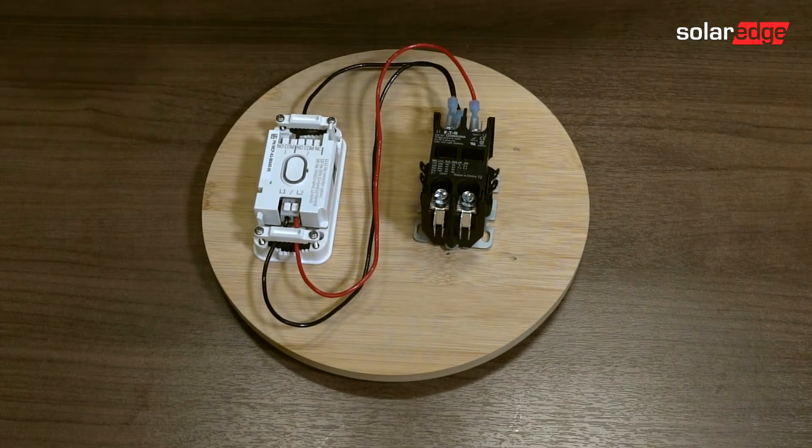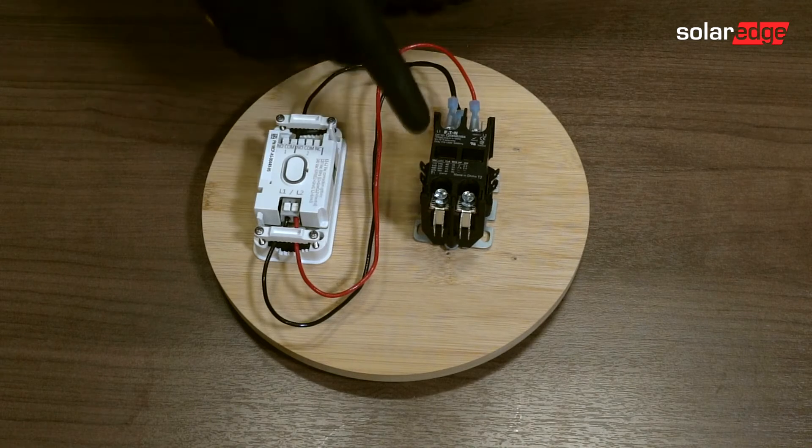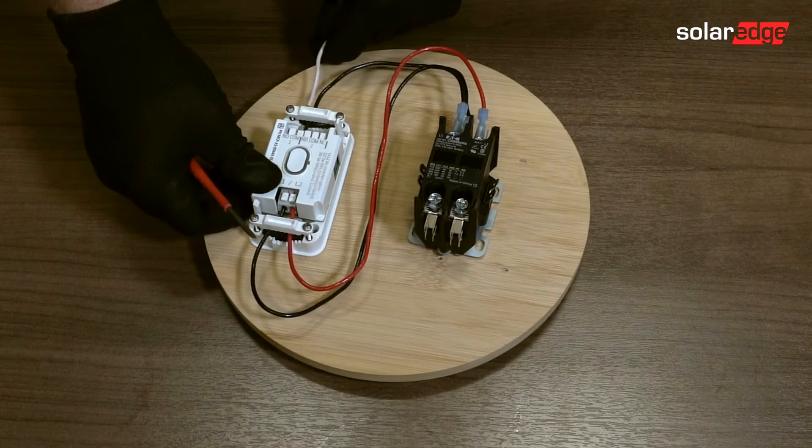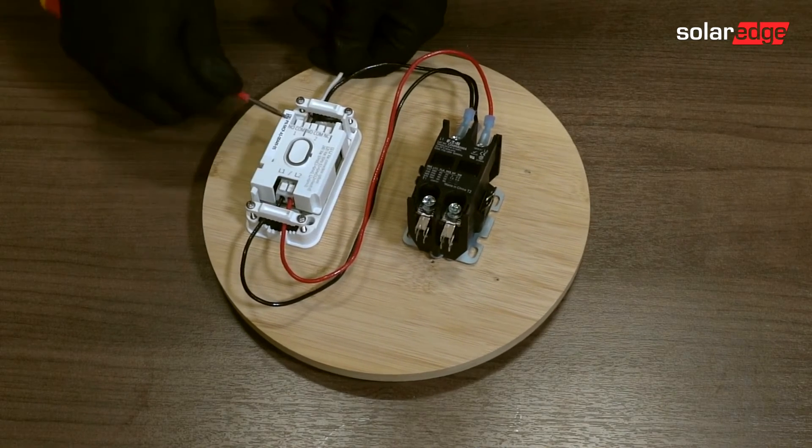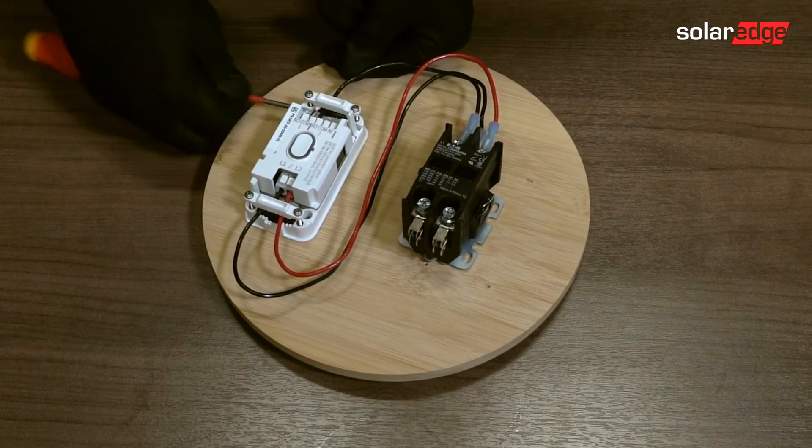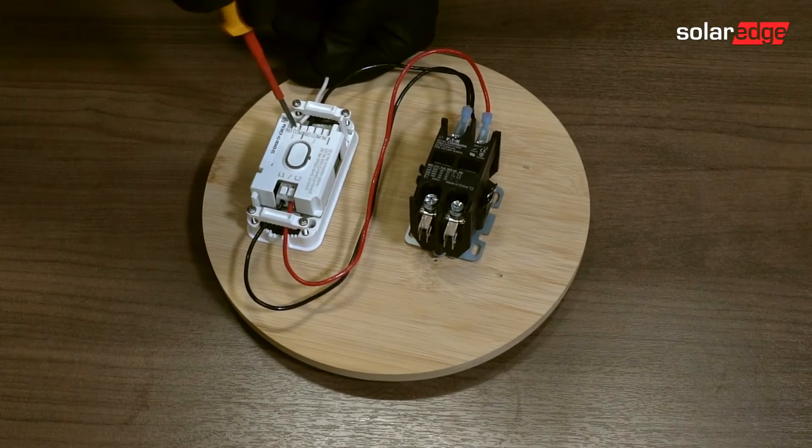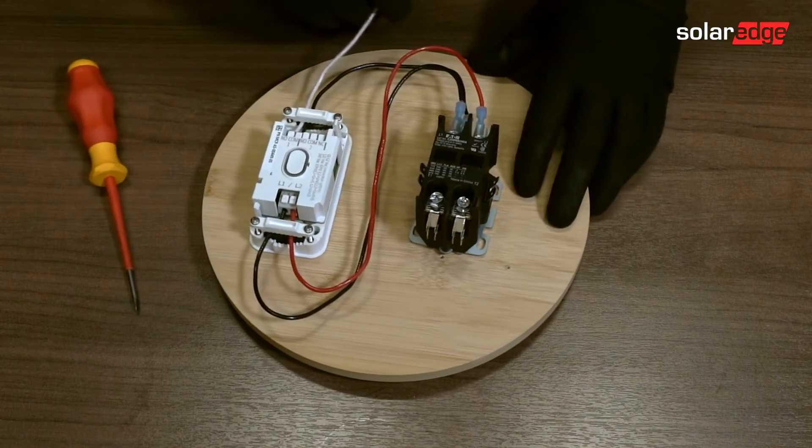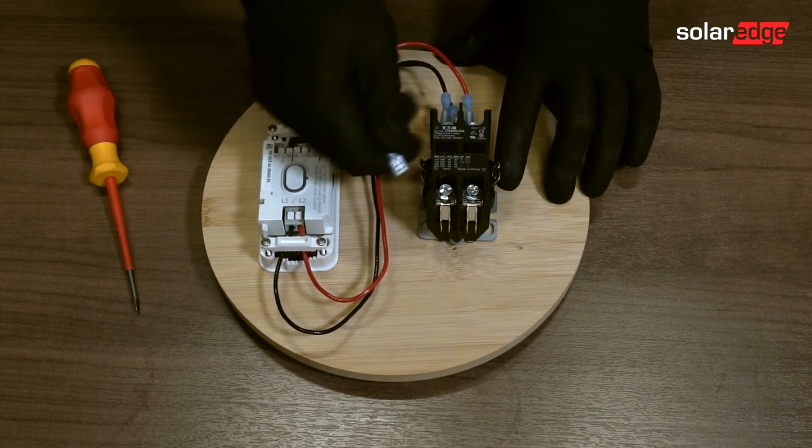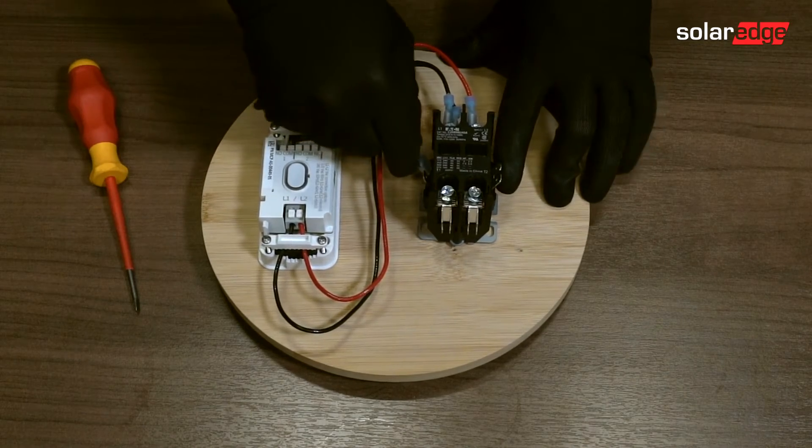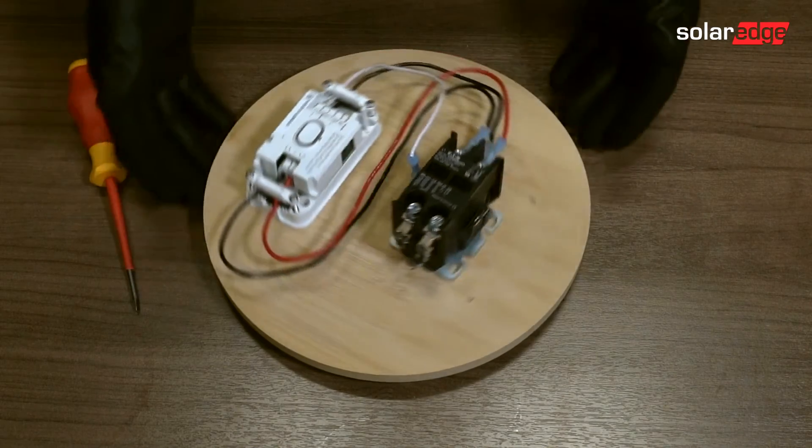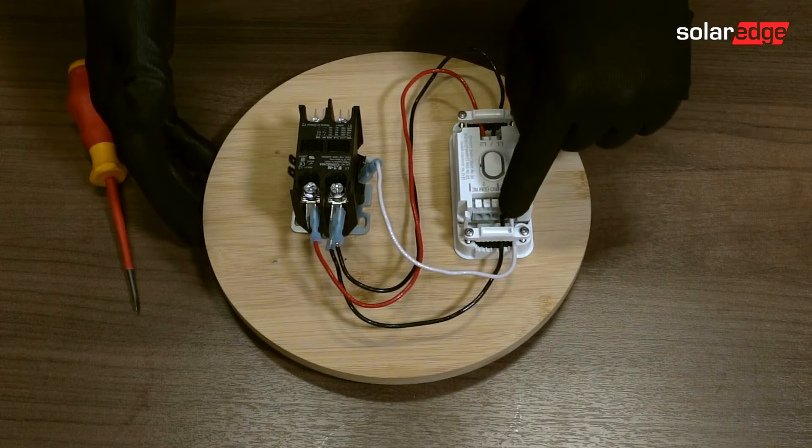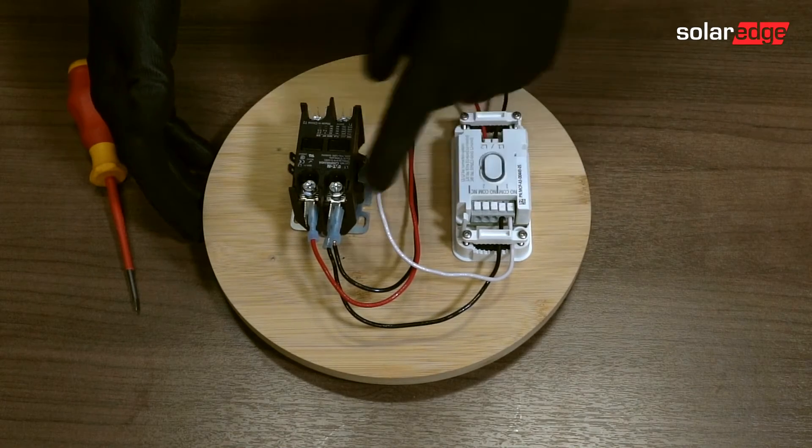And then we're going to wire our normally open to the coil. So I'm using a white conductor for the 120 volt coil to the normally open position. Again, push down on the pressure clamp, and we're going to go normally open to the coil. And then wire manage. Great. Let me give you a spin. So you can see normally open to coil and common to line one.